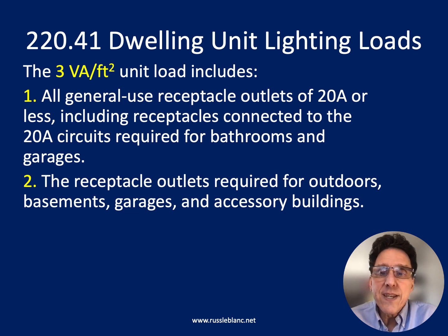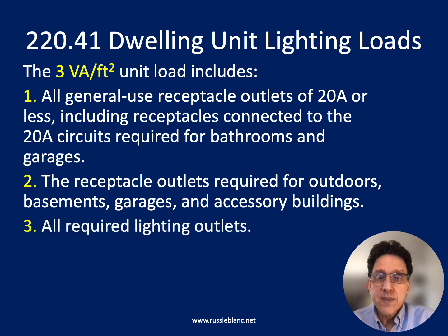Number two, the receptacle outlets required for outdoors, basements, garages, and accessory buildings, and all required lighting outlets are built into that 3 volt-amperes per square foot. So we don't need to add anything else. Everything's built into that 3 volt-amperes per square foot. There are no additional load calculations for any of these items.